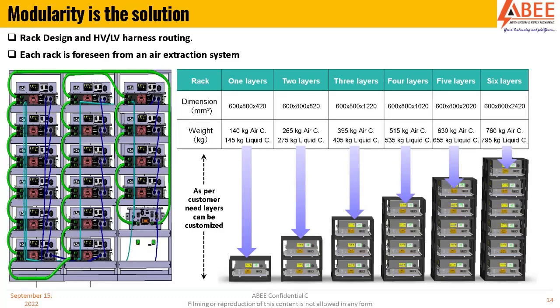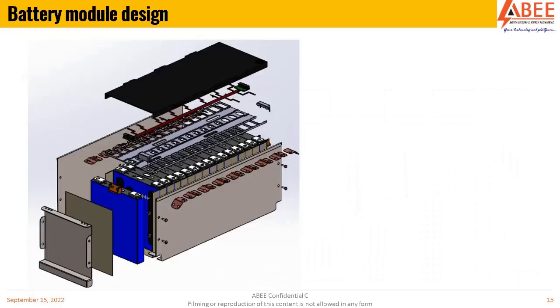Modularity is very important in this industry—meaning a solution that can easily be extended in terms of voltage or capacity without too many modifications. Here's an example: a rack system composed of modules of 5, 10, 15, or 20 kilowatt-hours, connected in series to reach higher voltage and in parallel to reach higher capacity. You can then dimension your battery system for different applications, which can be air-cooled, but increasingly, especially for large container batteries, we move to liquid cooling. In some areas of southern Europe and even the Middle East, air cooling no longer fulfills the requirements.